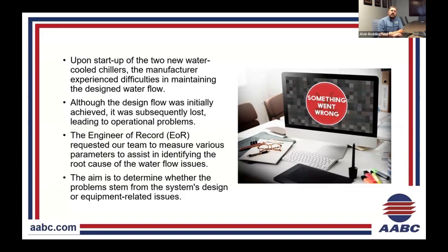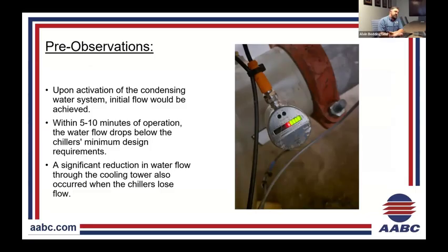They just really couldn't pinpoint it from the conversations with the mechanical contractor and the chiller manufacturer. So we were contacted to go out there and take some measurements for the engineer and see if there's anything we can assist with in the troubleshooting process to get the equipment started up. So on initial arrival to the project, we took a snapshot of what they were experiencing and tried to recycle everything. So we shut down the plant, let everything settle out, and then upon startup of the condensing water system, initial flow would be established.